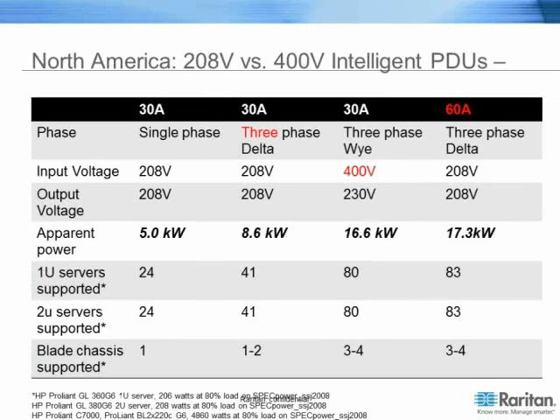Traditionally with North American PDUs, looking at what we can bring in single phase, we can bring in about a 5 kW load. That worked great a couple years ago. And we're still seeing customers that have cooling issues, that don't have the capability to cool a rack over 6, 7 kW.